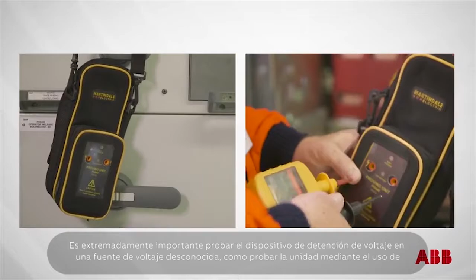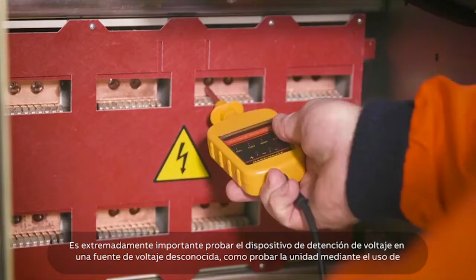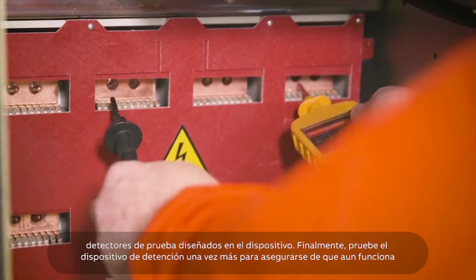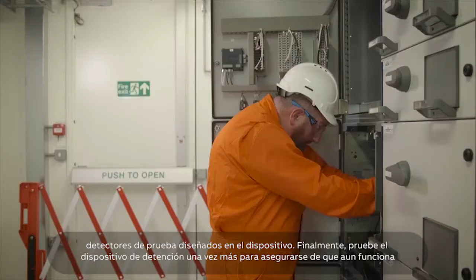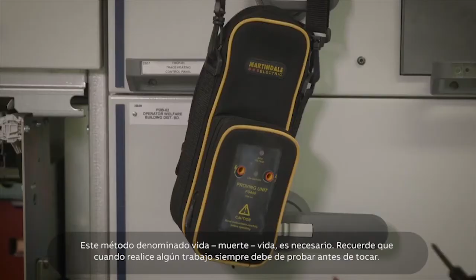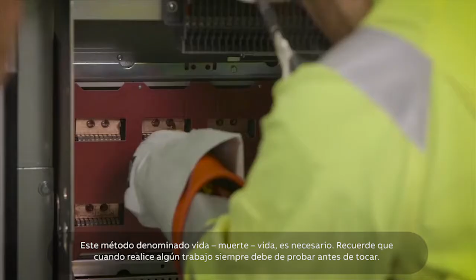It is extremely important that you test the voltage detection device on a known voltage source, such as a proving unit, or by using the detector's test button if designed into the device, then test for the absence of voltage. Finally, test the voltage detection device once again to ensure it is still working properly. This three-step method, often referred to as live, dead, live, is required without exception. Also remember, when carrying out the work, if you have any doubts, always test before you touch.